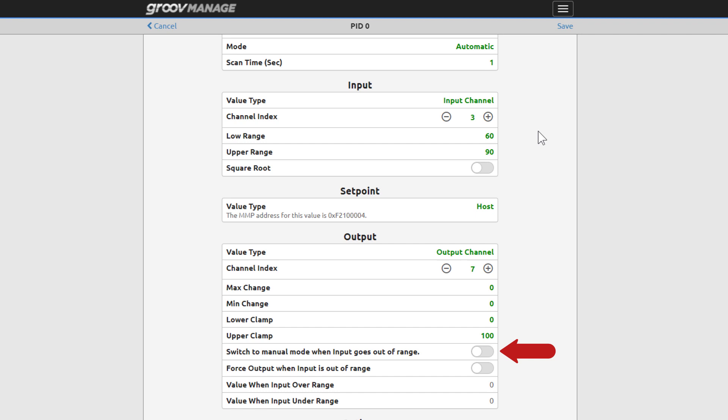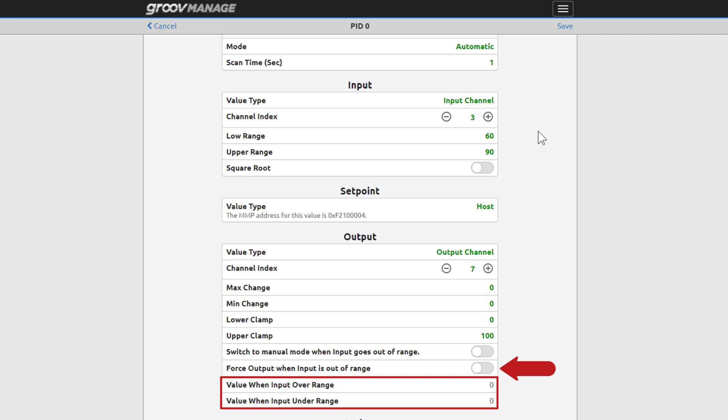Switch to manual mode when input goes out of range lets you switch the PID to manual mode until an operator or a host's logic assumes control, like Node-RED or a program running in the secure shell. The force output when input is out of range is only when the PID is in auto mode. You can set fixed values for the output when the input is under or over range. These options won't be used for this example. If the input goes out of range, the output value freezes at its current value. Changes to the output start up once the input gets back in range.